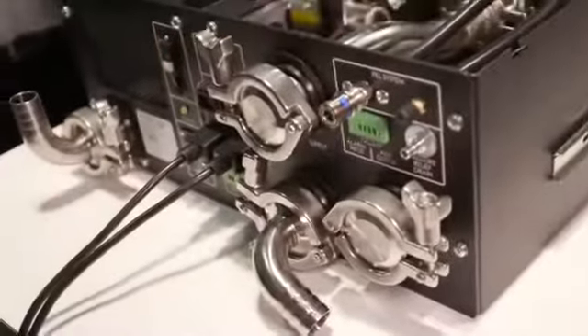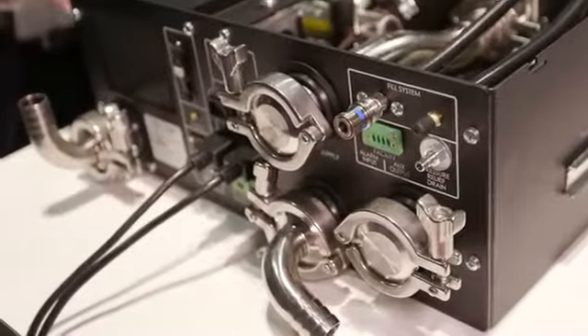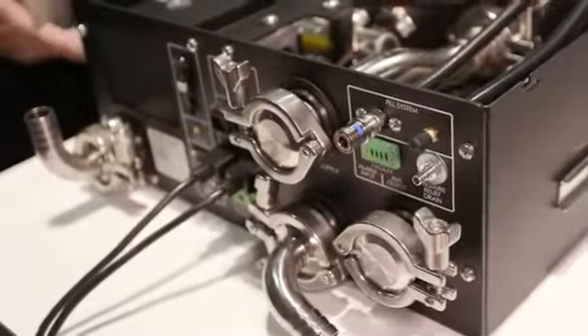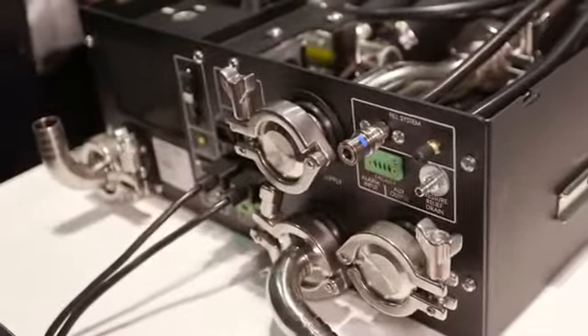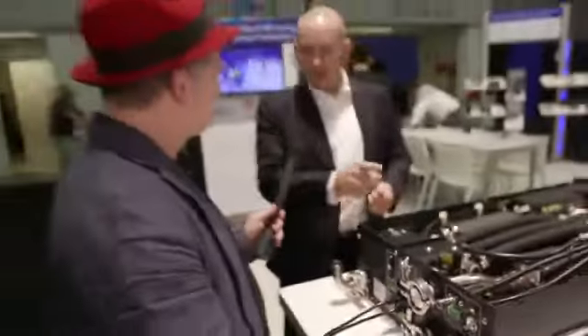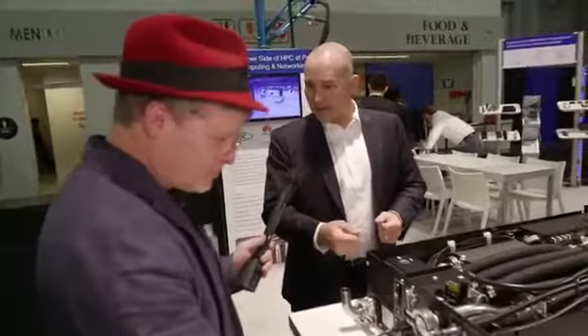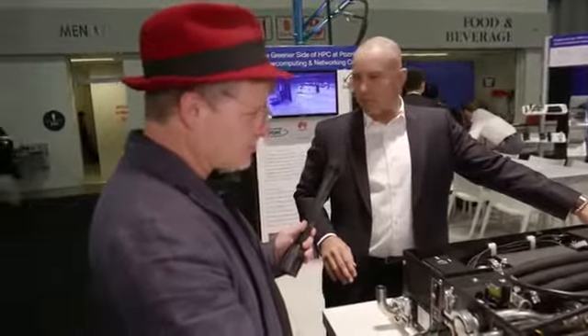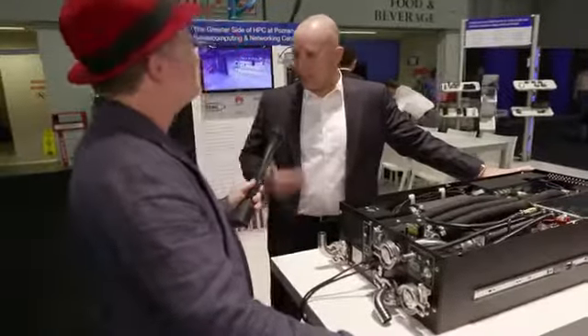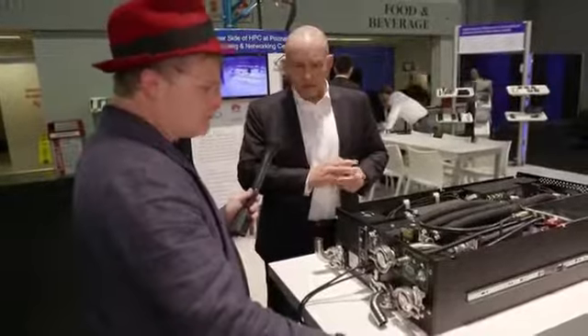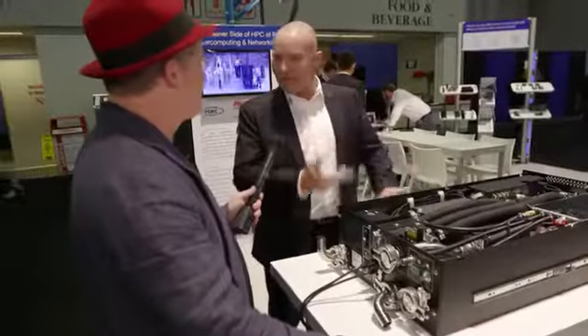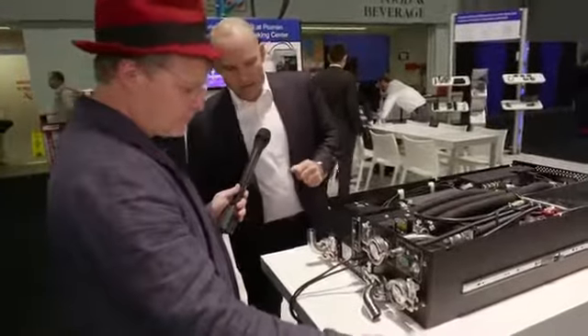The other additional handy feature for commissioning is that it has an automated fill routine put into it. So you connect up the fill pump and fill kit. We prefer to ship it full, but in some cases we go into an environment where they would prefer to fill it on site, which is okay. We now have an automated fill routine so that you hook up the fill and the bleed valve and the power switch right on here, and the control system controls that fill process so that we guarantee that we end up with a nice fill, and we don't have to have any special skills on site necessarily to service the unit. Dual redundant power supplies as well.